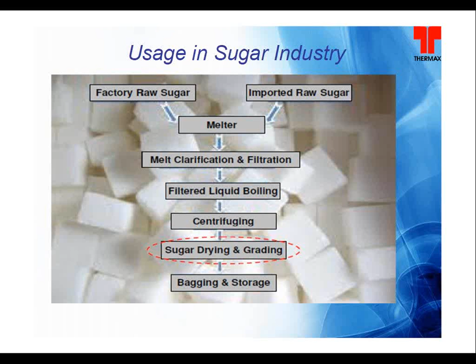This is a typical feasibility study for a 100 TR vapor absorption machine, compared with electrical compressors. Typically, electrical compressors in all the sugar industries are working on a reciprocating chiller. The typical power consumption of a water cooled reciprocating chiller for 100 TR is equivalent to 90 kilowatt. Whereas for a 100 TR vapor absorption machine, the running power consumption will be close to 1.3 kilowatt, and steam requirement will be close to 380 kg, considering 4 bar to 10 bar steam pressure and a cost of around 0.4 rupees per kg of steam after generating power.